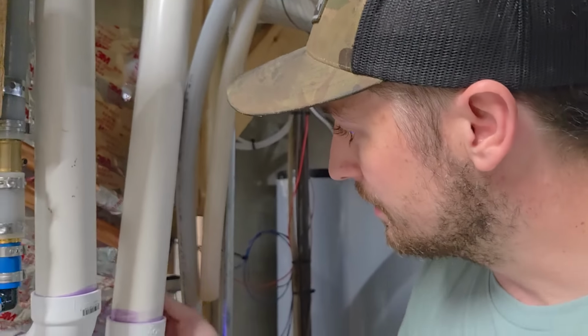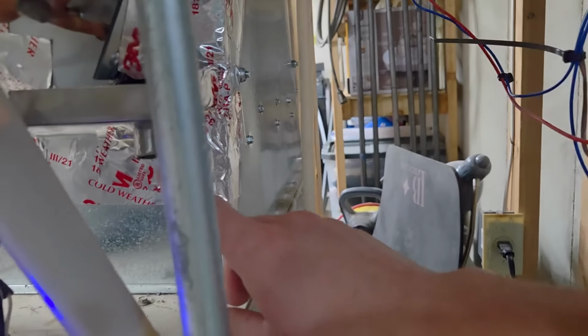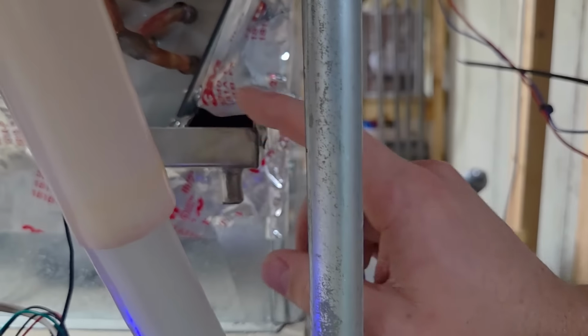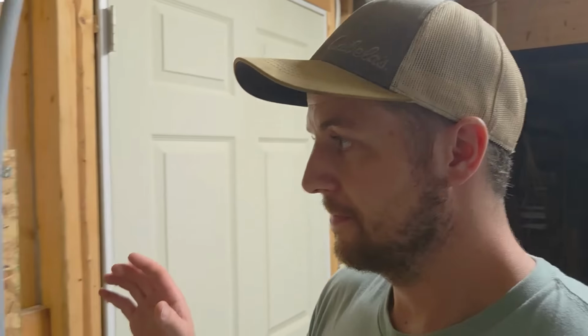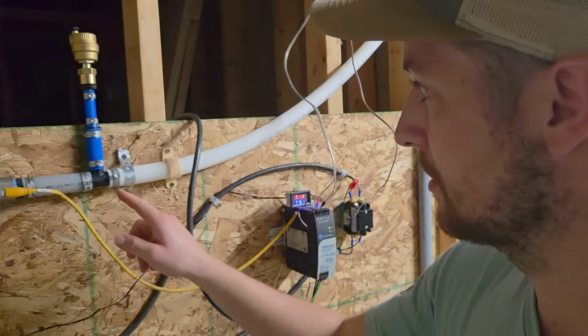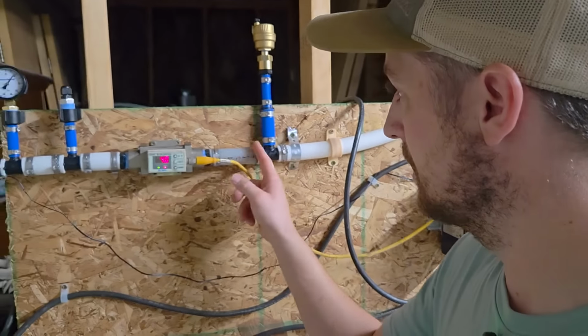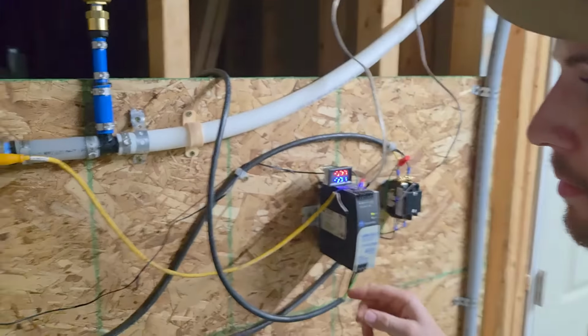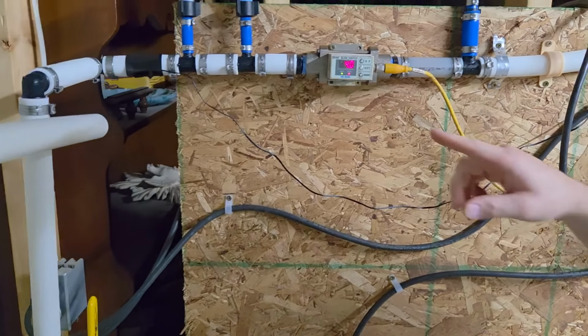I got a funny feeling this is gonna start to condensate, so I'm gonna hook up my drain line. It goes right there on my drip pan, goes down to the condensate pump down there. All right, so it's been running for about an hour and a half. I'm starting to get a little bit of condensation on some of these fittings and this plumbing. I'm reading 4 gallons a minute for water flow.